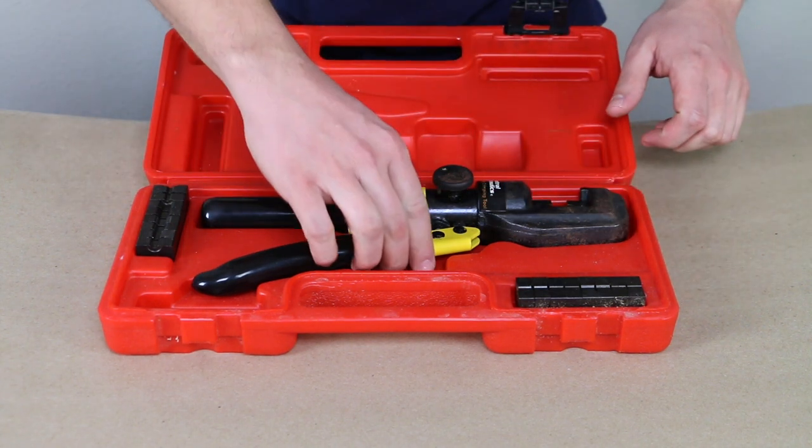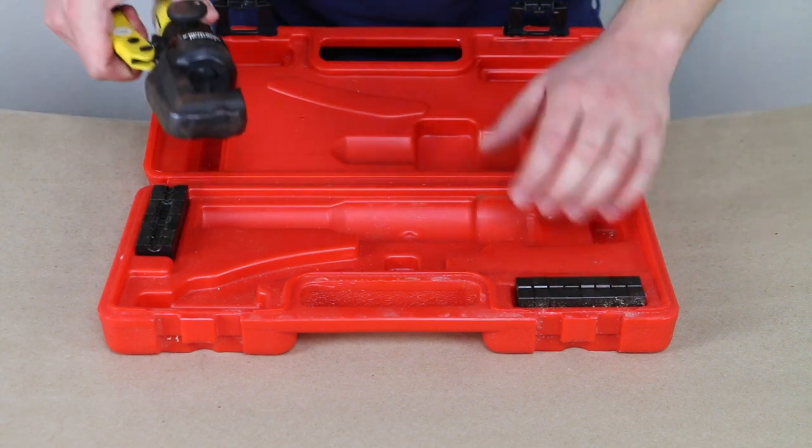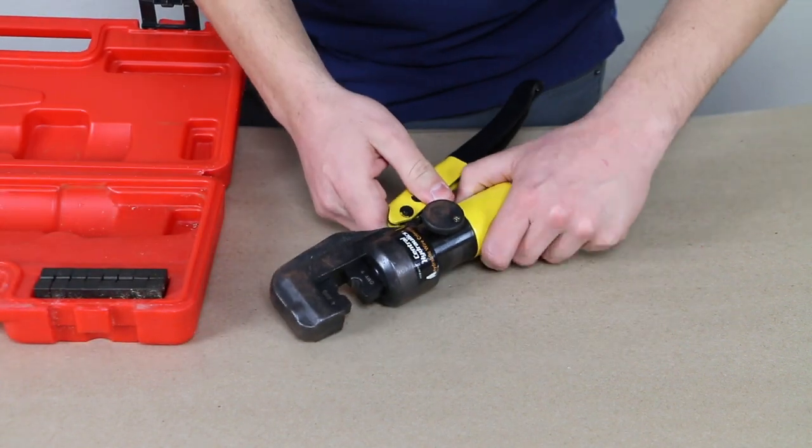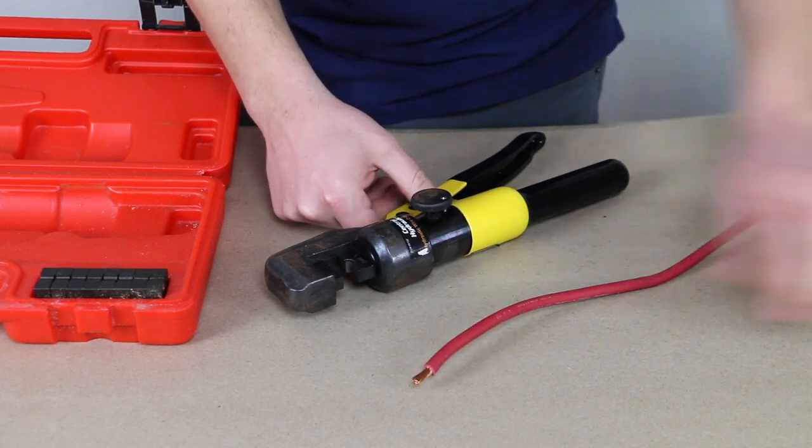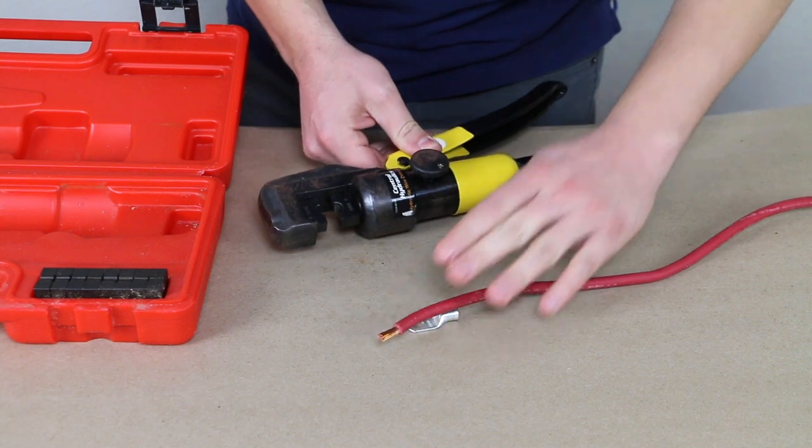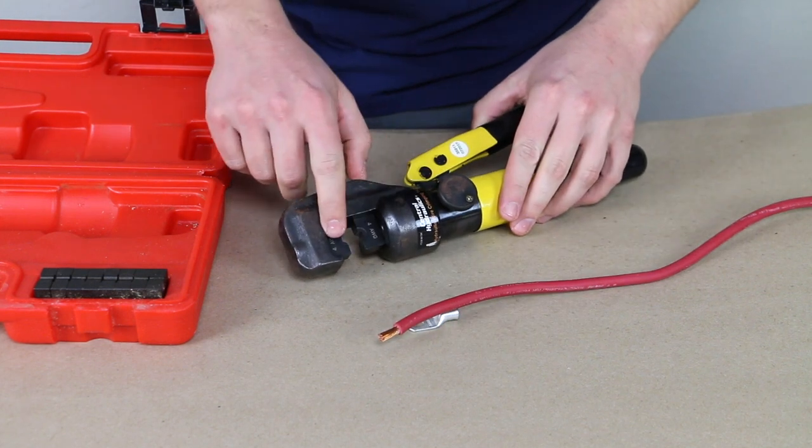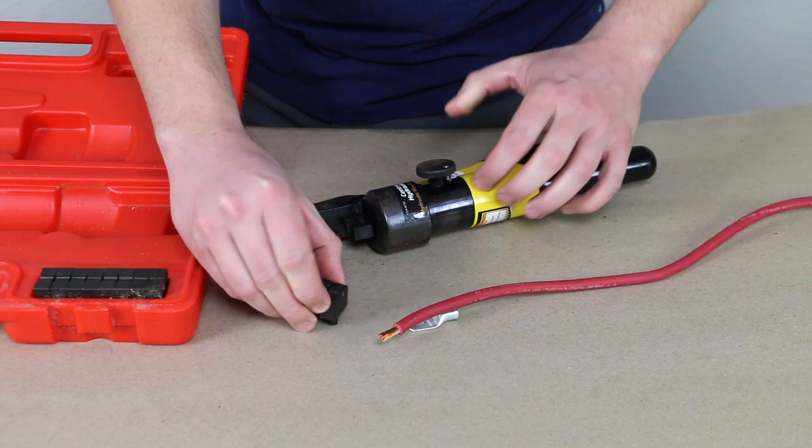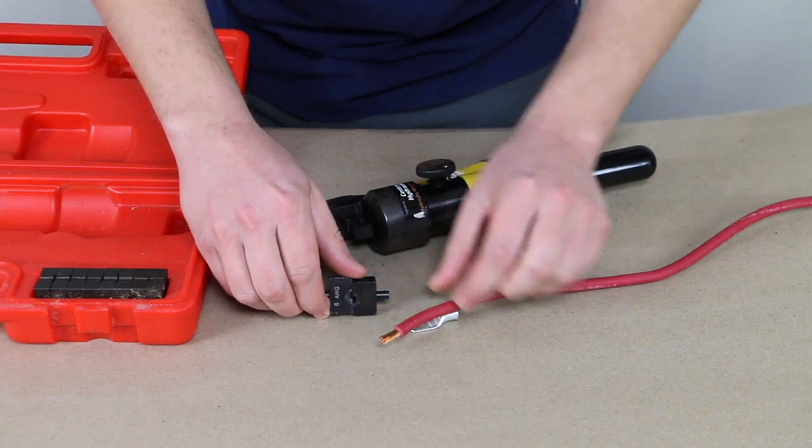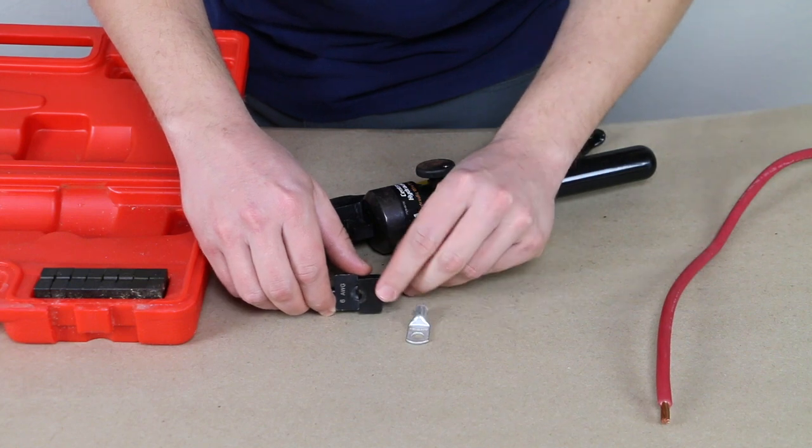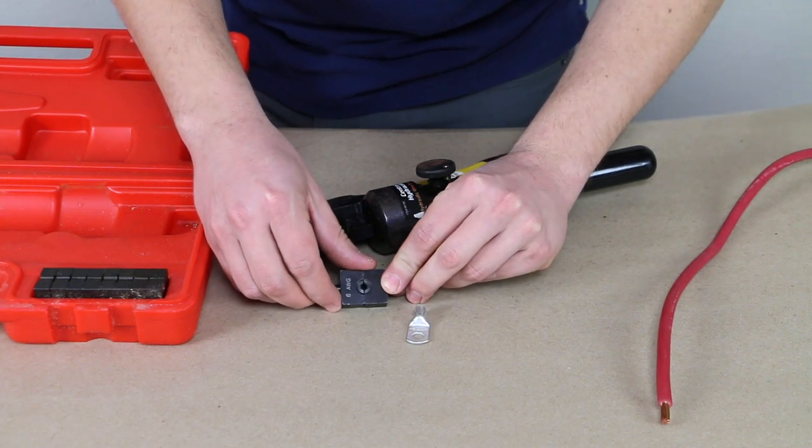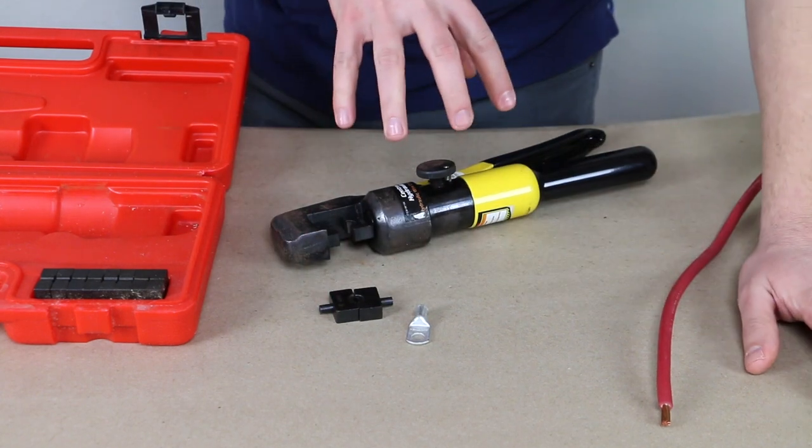So we are going to use the larger dies. Now, strike one for this crimper is we're using the same six gauge cable and terminal, but the dies, I'm going to have to use the four gauge dies. If we take a look at the six gauge dies, they are way too small for our terminal. I don't know if you can quite see, but they're just too small. End of story.